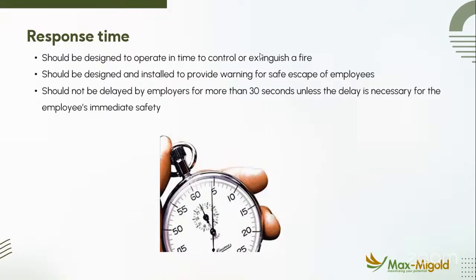Response time should be designed to operate in time to control a fire. In fact, for you to be able to escape from the fire or from the burning facility, it must be designed and installed properly. So your detectors should be designed and installed in such a way that they provide early warning for safe escape of employees and visitors. Also, if there is a delay of more than 30 seconds, maybe from the smoke detectors and what have you, this should be quickly addressed because the purpose is not for any delay to happen. The purpose is for the smoke detectors to actually react on time and people can also escape in good time. Next slide.